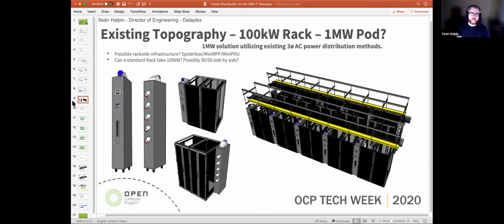In my mind, how would you have a 100 kilowatt rack? If someone were to come to me today and say, I have a requirement for 100 kilowatt load, when we were first thinking about this, I was thinking you could have two 50 kilowatt on-chip or liquid cooled racks. You would have your overhead encapsulated busbar or high amperage busbar, then feed down into almost like a mini RPP that would sit beside the racks.